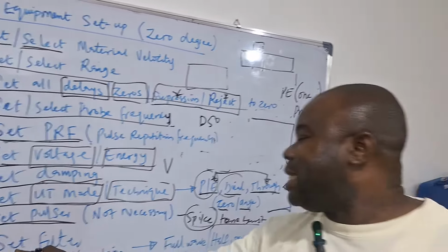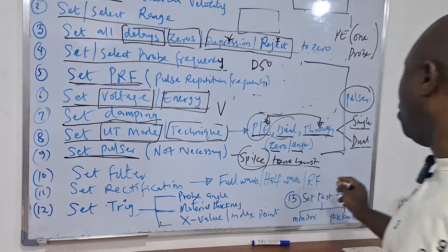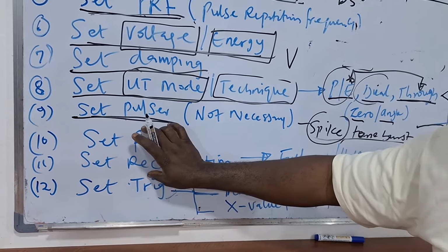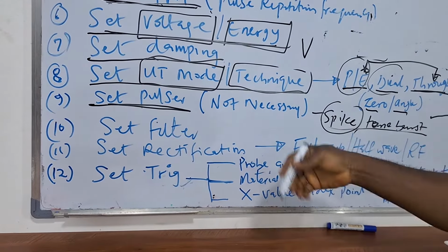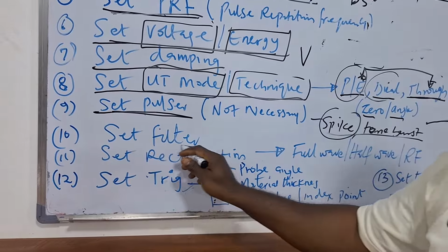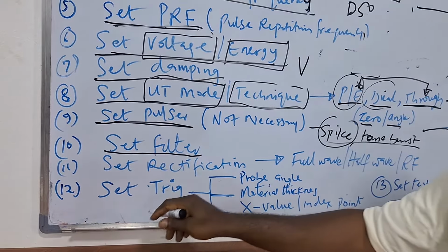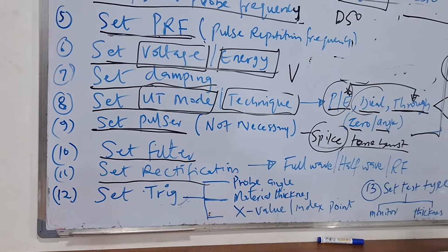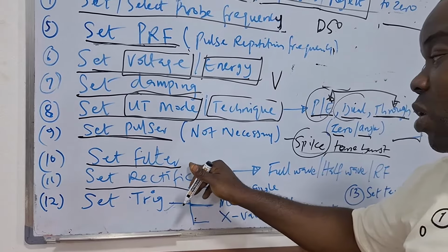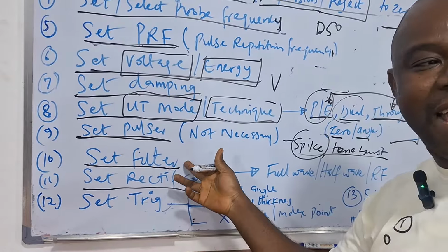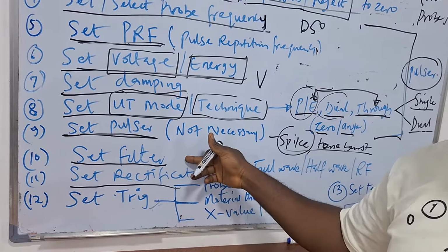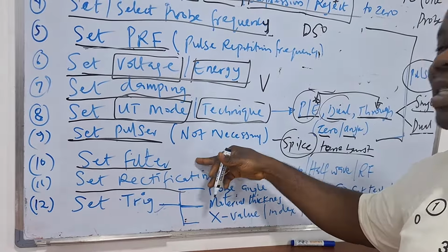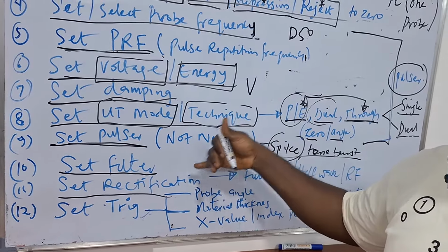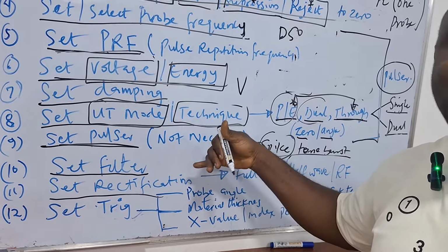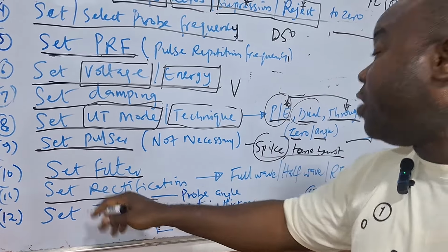Number 10 and 11 has to do with the receiver, which is your output signal coming from the UT machine. The options available are your filter and your rectification. Your filter, as I always advise, leave alone if you don't understand what it does. Don't start setting your band passes, your high pass, and your low pass - you'll get yourself into trouble. Just leave it alone if you don't know what to do.